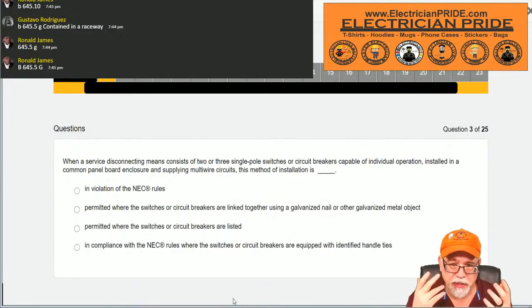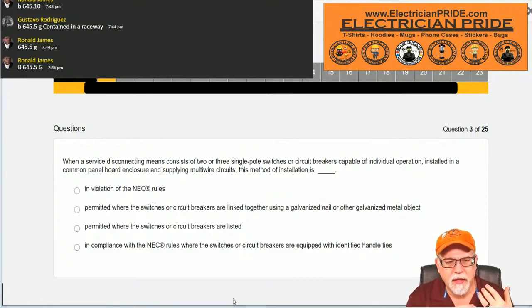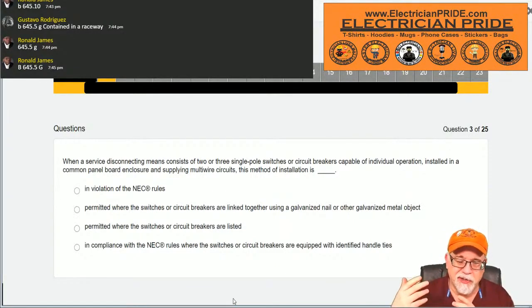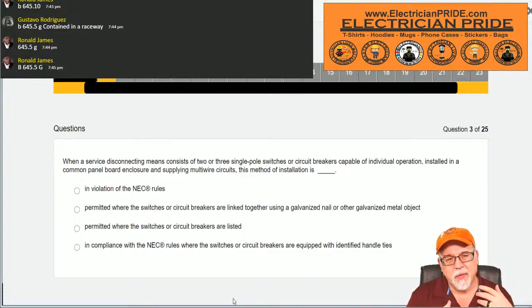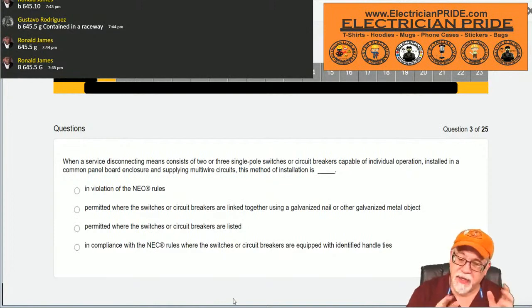Now let me dissect it while y'all are looking this up. Okay, so it says - now this one might be a little tricky, we'll see how this turns out. It says where a service disconnecting means consists of 2 or 3 single pole switches or circuit breakers capable of individual operation installed in a common panel board enclosure and supplying multi-wire circuits, this method of installation is - now this is a weird question because it's talking about multi-wire circuits, yet it starts out by saying where the service disconnecting means consists of 2 or 3 single pole switches or circuit breakers. So I'm not sure I like the wording of this question, but let's see where it goes.